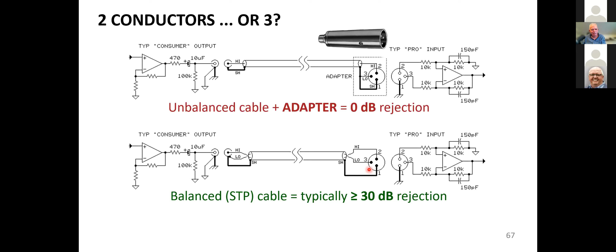Now, going the other way, this is bad. This is a dilemma, because there's 3 basic different types of output stages. There's the voltage-driven outputs, which are very, very common. There's the newer electronically balanced outputs, where theoretically you can ground one of the outputs without hurting anything. And there's a true transformer output. Now with these, here you can't ground one of these outputs, or you're going to overheat and possibly damage one of the drivers. It'll see a short. Over here, you should ground one of the outputs because the common mode impedances are high and undependable.